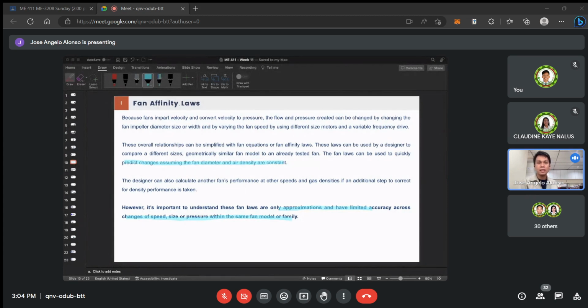So it will be used as a guide lang para ma-predict yung changes ng speed, size, or pressure ng ating fan once na bago natin ang diameter ng ating impeller o ng ating fan, o binago natin o replace natin ang motor na ginagamit. Pero hindi lang pala yung class ang pwede natin gawin. We can change the fan size but maintain the speed ng motor, or we can change the speed ng motor but maintain the fan size, or we can change both of them. Pwede natin palitan parehas yung diameter ng fan at at the same time, palitan din natin yung motor o ibahin natin yung speed ng ating motor. So that is 3 fan affinity laws na lang.